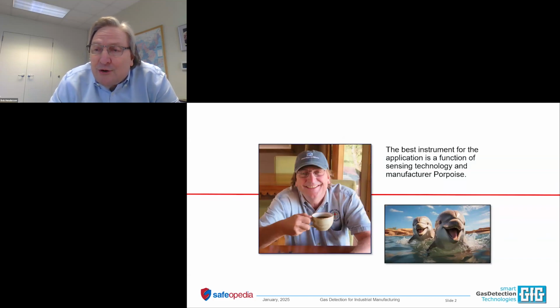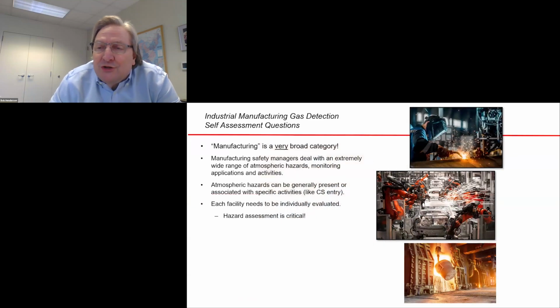But whether it's fixed or portable, the common drumbeat throughout my presentations is that when you're thinking about gas detection, the best instrument for the application needs to be a function of sensing technology, a function of the manufacturer's purpose, what the design was created to do, and your needs. So let's see if we can do a good job, or the beginning of a good job, of figuring out what your gas detection needs actually are.